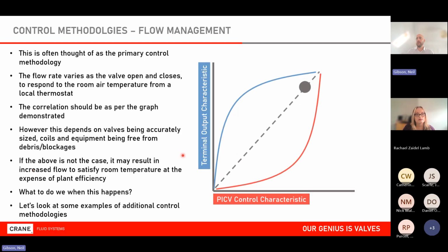So this is our traditional 0 to 10, 0 to 100% control here based on what we believe the flow output will be. So here's my heat output from the coil. It's this kind of shape. My valve usually is equal percentage. It's doing the opposite. So I drive 0 to 10 volts on a nice linear resultant curve. The issue here is that when it drives, the position it believes it's in is generating a flow rate to give us a power output. If, for example, my delta T is significantly compromised for whatever reason, blocked coil, some issue elsewhere in the power generation, despite the fact it thinks it's generating a power output based on the flow rate, it's not. So it'll be generating a flow rate without any real indication that the user's getting the required heat output.